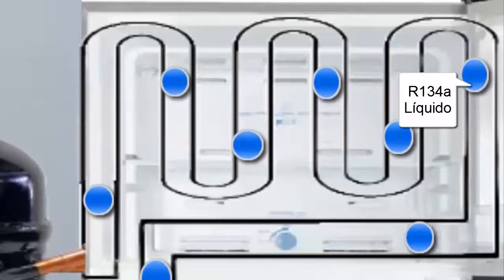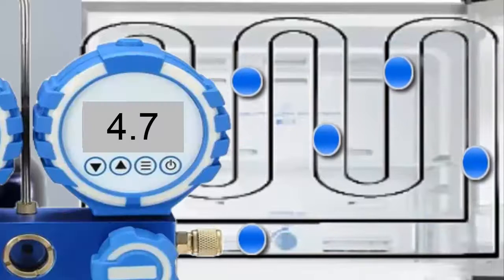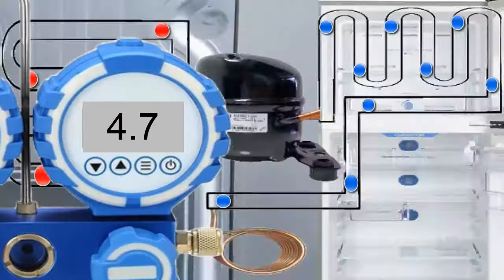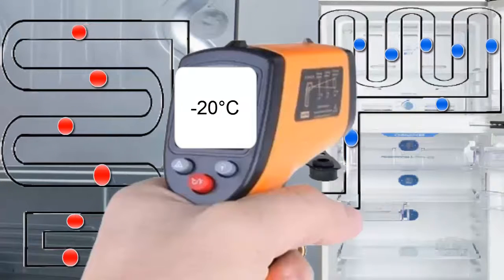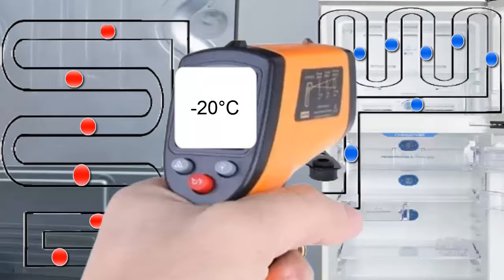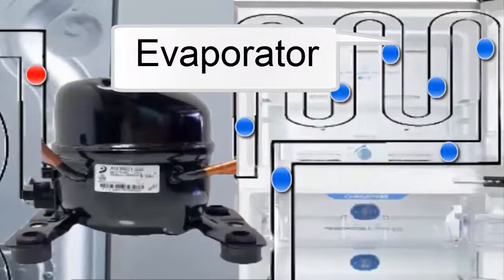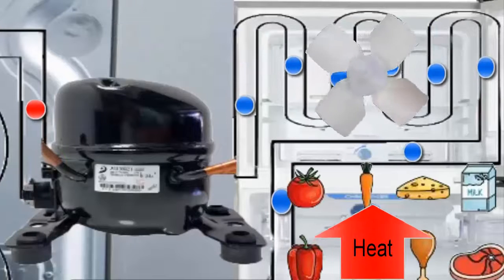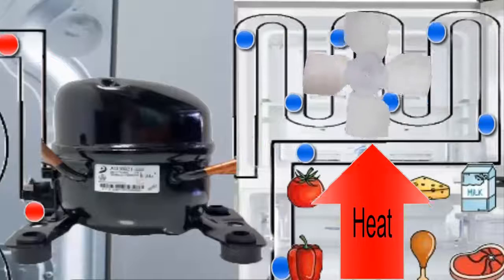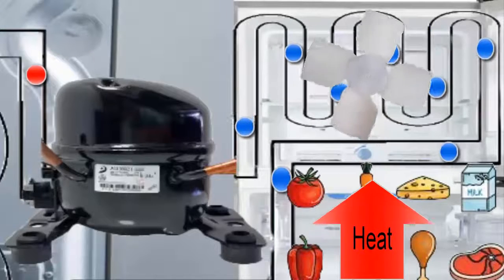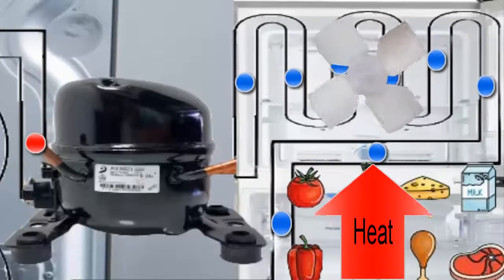The R134A refrigerant enters the evaporator in a liquid state at a pressure of 4.7 pounds per square inch. With this pressure, it is achieved that the R134A in the evaporator has a temperature of minus 20 degrees Celsius. With this low temperature and with the help of the fan, the heat from the food quickly passes to the R134A refrigerant, causing it to evaporate.